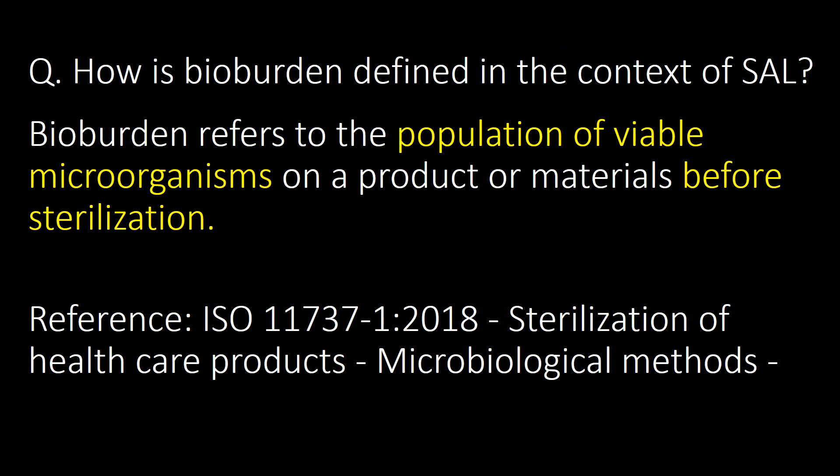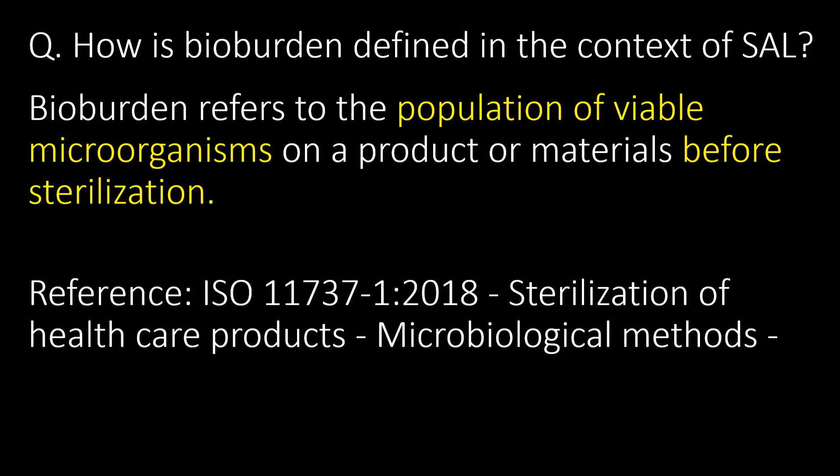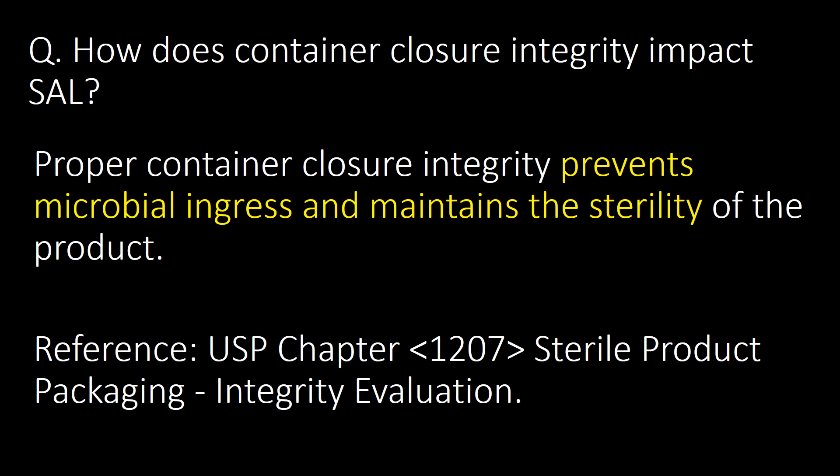How is bioburden defined in the context of SAL? Bioburden refers to the population of viable microorganisms on a product or materials before sterilization. Reference: ISO guideline. How does container closure integrity impact sterility assurance level? Proper container closure integrity prevents microbial ingress and maintains the sterility of the product. Reference: USP Chapter 1207.